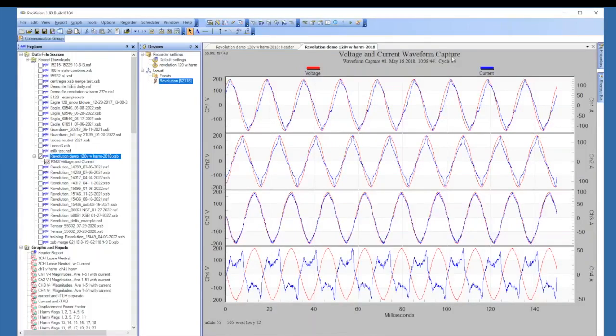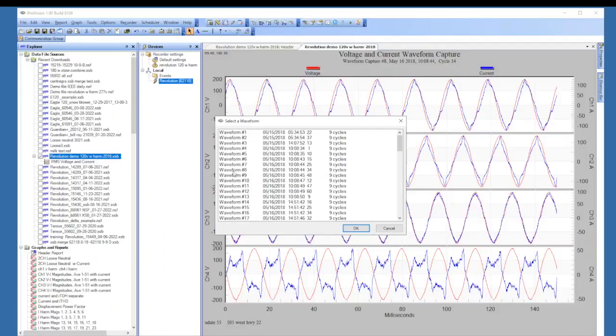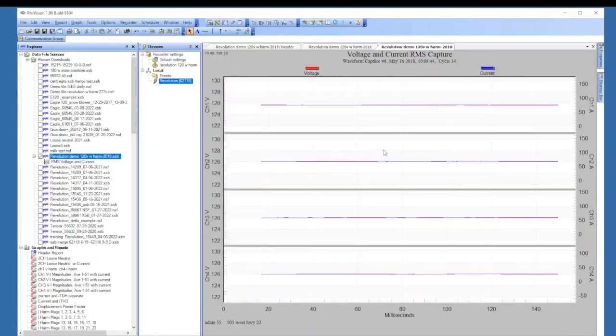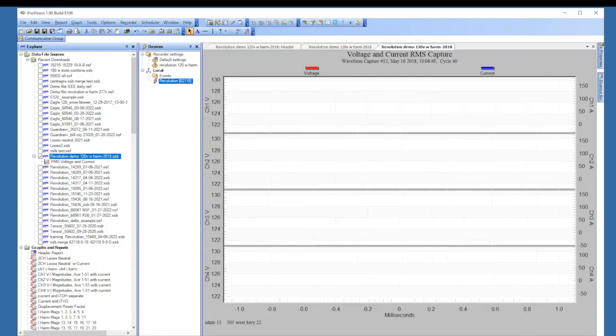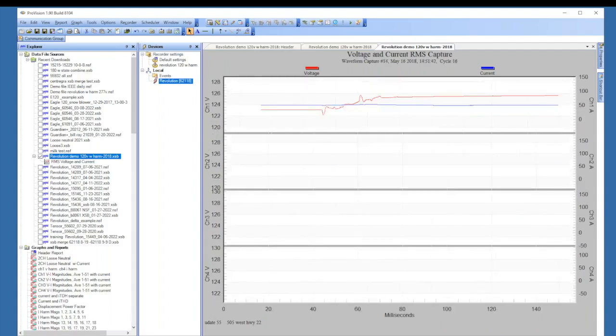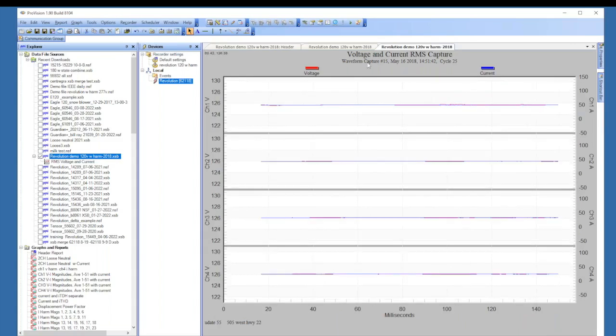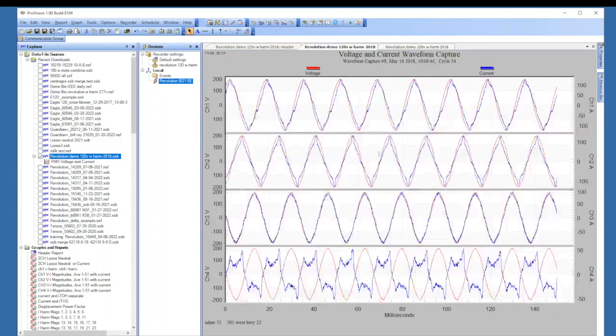So by default, you get the standard waveform capture, but under the graph tab, in the peak to peak, you can't really tell from one cycle to the next how much the voltage really changed. But if you go down to the waveform capture, there's actually an RMS capture. So if we click on the waveform 8, then we have nothing too exciting, but we have the RMS voltage there. And then you can compare those and see how much voltage it changed.